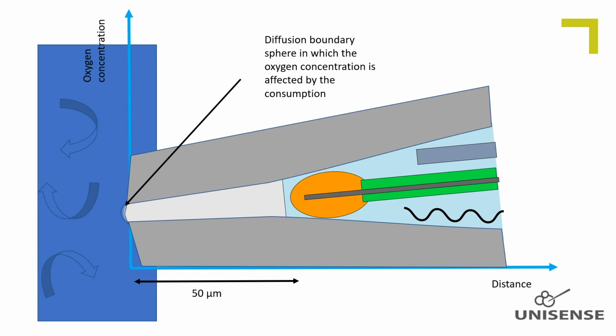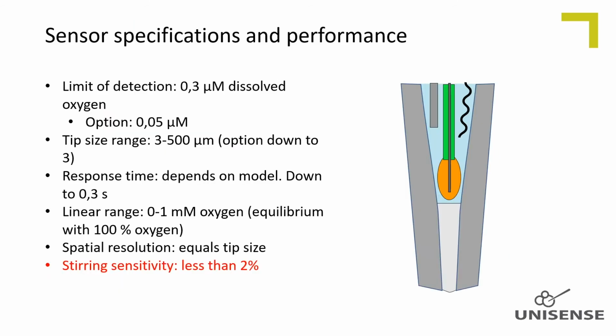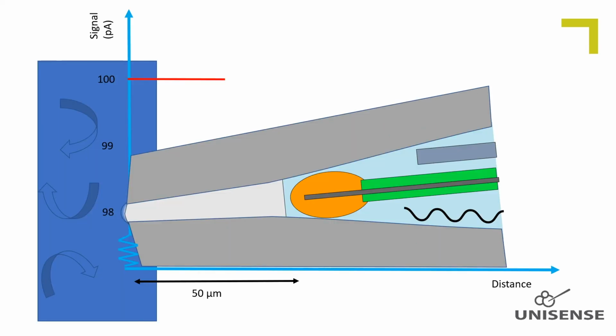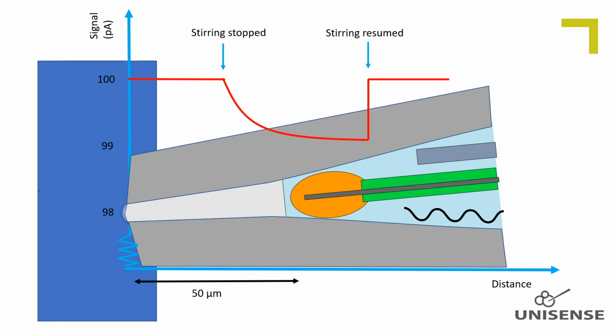But physical disturbance, which increases with tip size, should also be considered when profiling in biologically active matrices. The sensitivity to stirring is for standard sensors less than 2%. The sensitivity to stirring is defined as the difference between the signal in stirred and stagnant sample with the same oxygen concentration. This is exemplified here, where a sensor measures in a continuously mixed sample. When the stirring is stopped, the signal decreases about 1%, which is typical for an oxygen sensor. And when the stirring is reactivated, the signal is back to the original level.